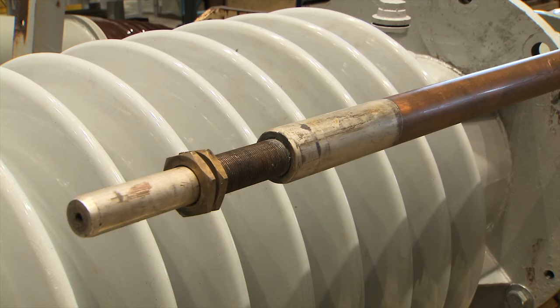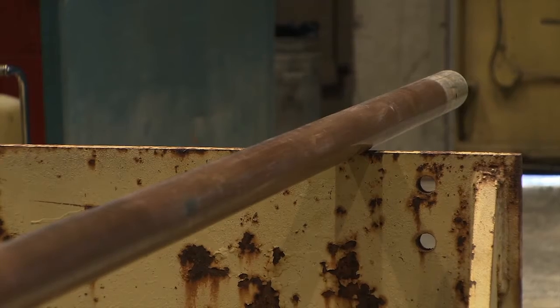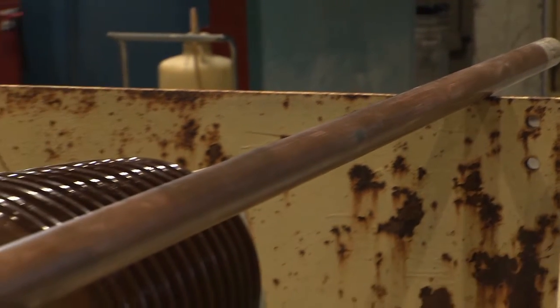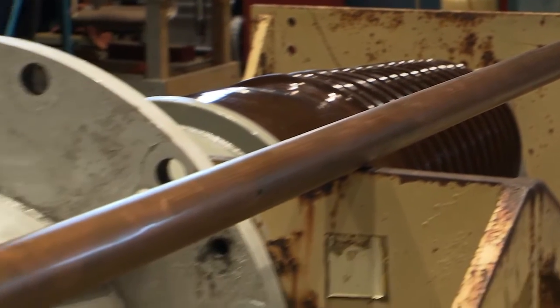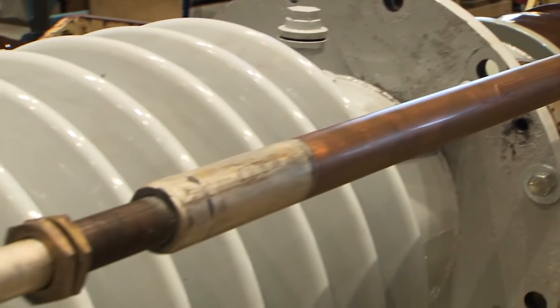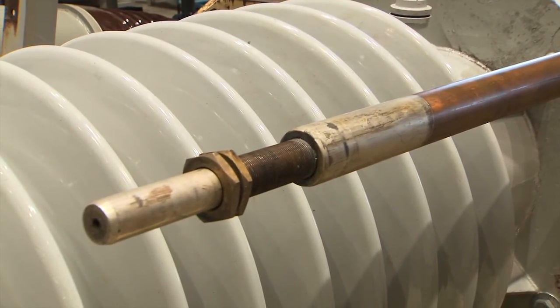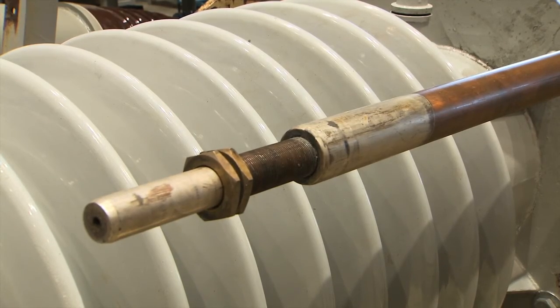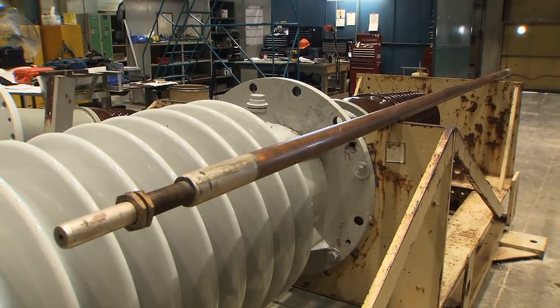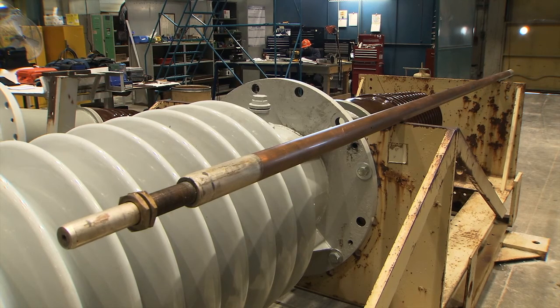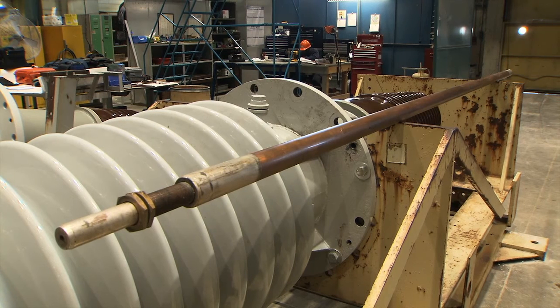The current rating on the draw lead conductor supplied with the bushing by the bushing manufacturer is dependent upon several factors. These are conductor cross-section and material, how the conductor is connected to the top terminal of the bushing, threads or multi-spring contacts. If the conductor is two-piece, the type of joint used, bolted or threads. Top oil temperature, oil level in the transformer, oil level in the bushing central tube, ambient air temperature.